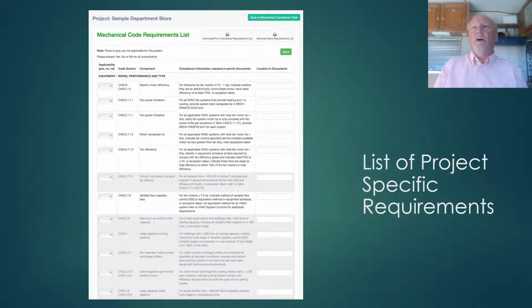So here's an example of our mechanical code requirements list. Based on the answers to the questions that you input in the general mechanical information page, it will then identify which specific components and control requirements are required for your project. If it's a component that's not required, for example, in this case, anything that deals with Group R occupancy, if you don't have a Group R occupancy, then all those requirements specific to Group R are grayed out. They don't apply to your project, but they're not eliminated. They're still there, but they're just grayed so that you only have to deal with the components that are in bold text.